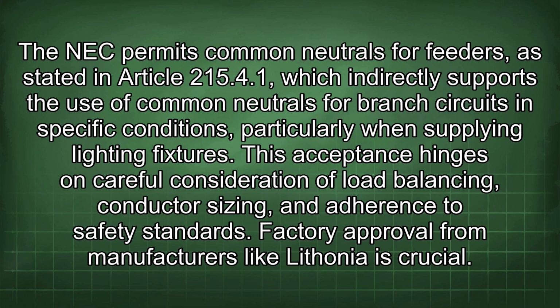The NEC permits common neutrals for feeders, as stated in Article 215.4(1), which indirectly supports the use of common neutrals for branch circuits in specific conditions, particularly when supplying lighting fixtures. This acceptance hinges on careful consideration of load balancing, conductor sizing, and adherence to safety standards.